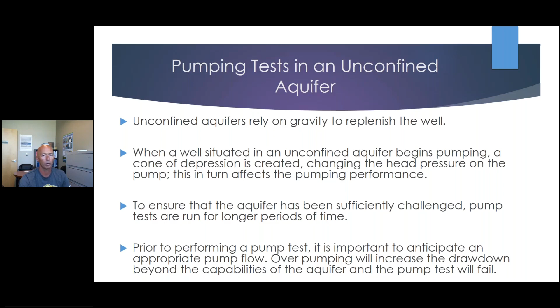Prior to performing a pump test, it is important to anticipate a proper, appropriate pump flow. Over pumping will increase the drawdown beyond the capacity of the aquifer, and the pump test will fail. So we want to tax the well, but we also want to make sure that we're not overtaxing the well. We want to bring that level down to where it starts to stabilize out, and then we start to assess that we have enough water replenishing into that well that we can move forward with construction of the well.